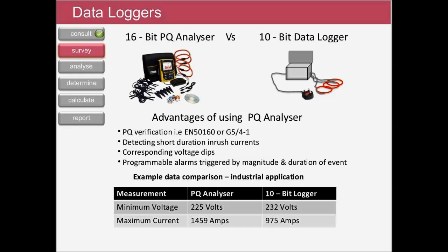I collated the data in this table here on a site where I actually used both types of logger together at the incoming terminals, on the LV terminals that is. As you can see here, the results recorded by these units are significantly different, and although the variations can be attributed to relatively short-term infrequent events, misunderstanding these characteristics can lead to the stability of the equipment being compromised. Now this will be covered in more detail shortly, but before that I'd like to run through some of the very basic criteria that should always be looked at as part of the survey.